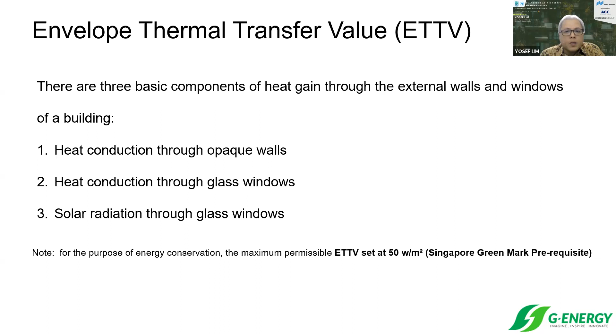This ETTV will have a relationship with the building cooling load. If you have a higher ETTV value, your building will require more cooling load to make the indoor air more comfortable. Because of that, the building will consume more power for cooling comfort. That's why ETTV is quite important and critical, especially for buildings in tropical countries.